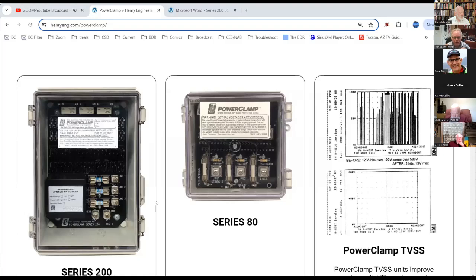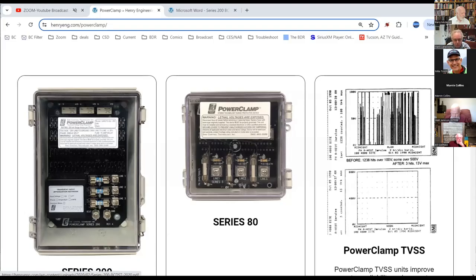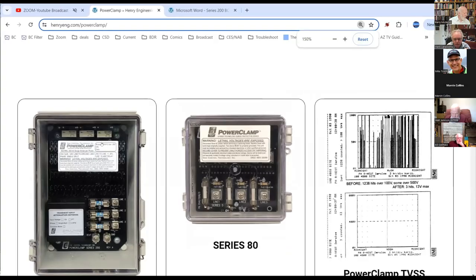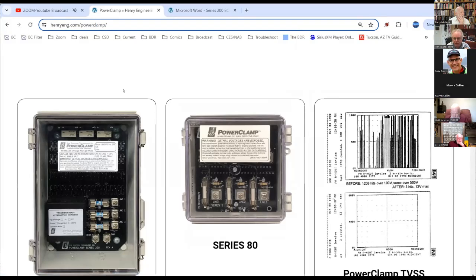Hank, let me ask a question then. You talk about this being in parallel. Is there an alarm circuit here to let the user know when one of these fuses goes out? Yeah, there is. You can get a relay option that will let you know. If you look at the series 200 up here at the top, you see these three white things, those are relays. So if any of these fuses down here blows, one of those relays will open up and give you a contact closure, which you can interface to your transmitter remote control and give you some kind of an alert back at the studio that you've lost a fuse.